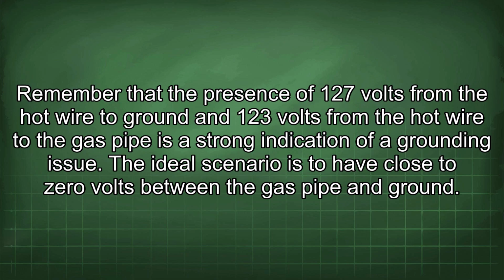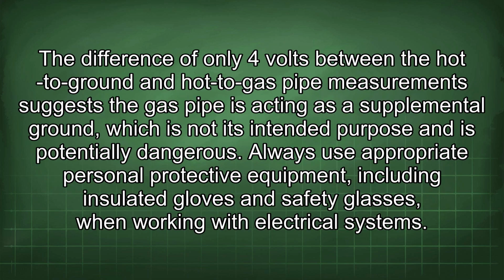Remember that the presence of 127 volts from the hot wire to ground and 123 volts from the hot wire to the gas pipe is a strong indication of a grounding issue. The ideal scenario is to have close to 0 volts between the gas pipe and ground. The difference of only 4 volts between the hot to ground and hot to gas pipe measurement suggests the gas pipe is acting as a supplemental ground, which is not its intended purpose and is potentially dangerous.